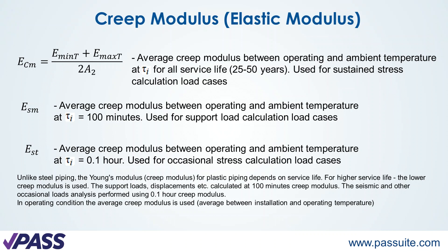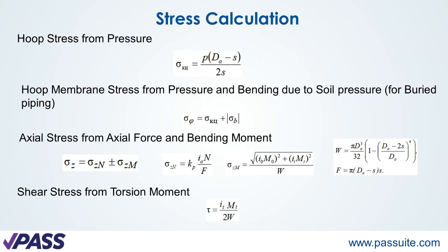The third creep modulus is calculated for one-tenth of an hour and is used for occasional stress calculation. The hoop stress from pressure load is calculated by this equation, and bending moments are also included.